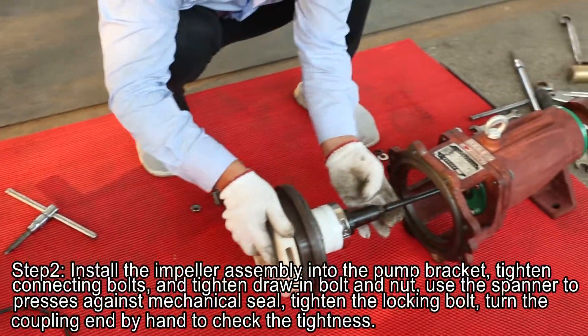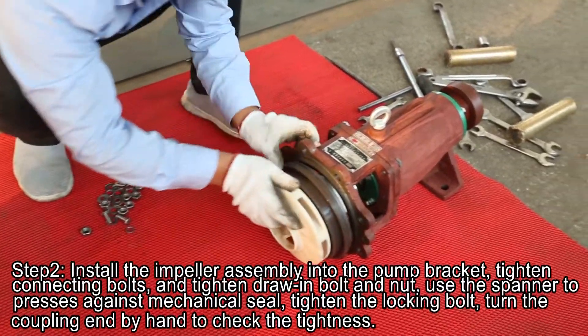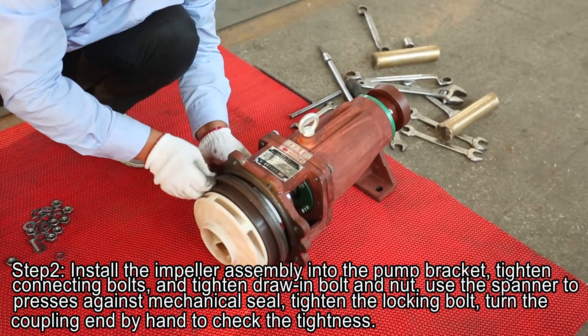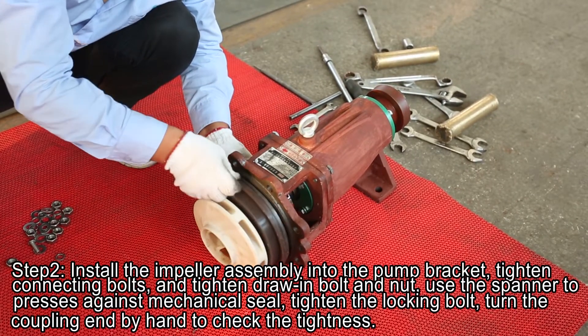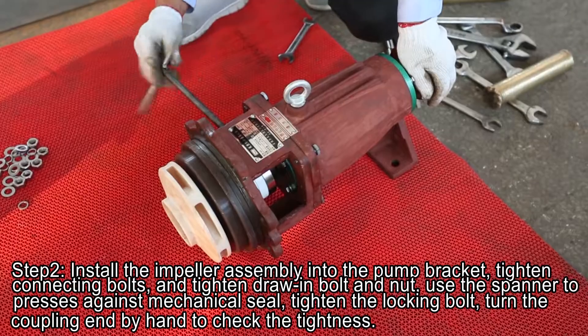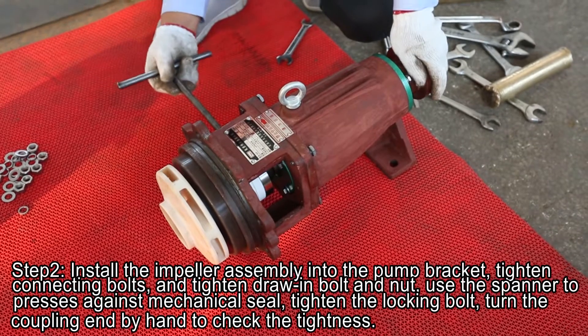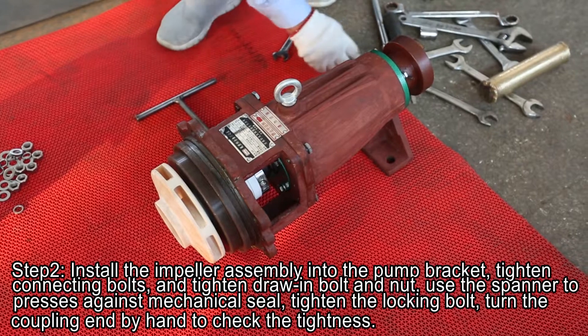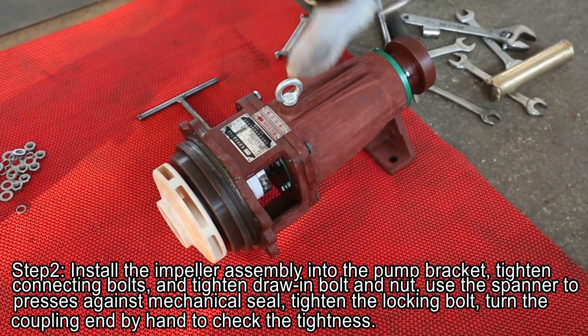Step 2. Install the impeller assembly into the pump bracket, tighten connecting bolts, and tighten draw-in bolt and nut. Using the spanner to press against the mechanical seal, tighten the locking bolt, turn the coupling end by hand to check the tightness.